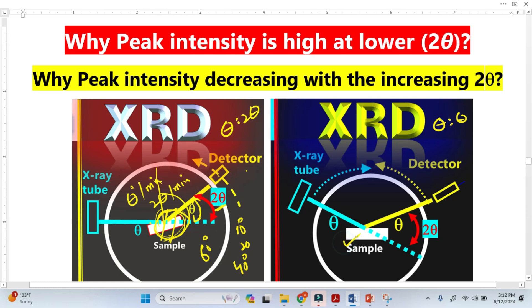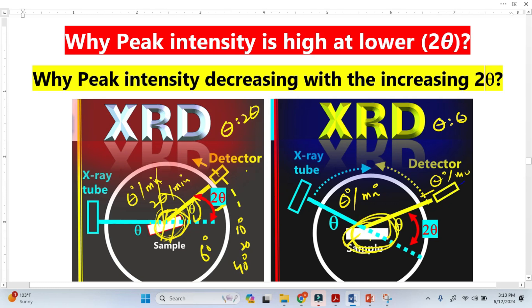Now let's explain from the Theta versus Theta setup. Here the sample is stationary. The X-ray tube is rotating Theta per minute, and the detector is also rotating Theta per minute. At lower 2-Theta, we can see there is a large volume for the incident X-ray, giving a higher scattering probability for the incident X-ray at lower 2-Theta.